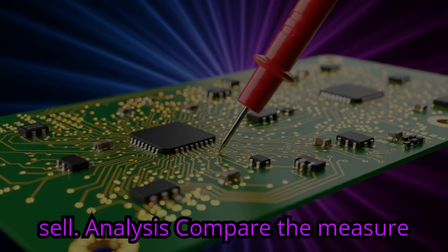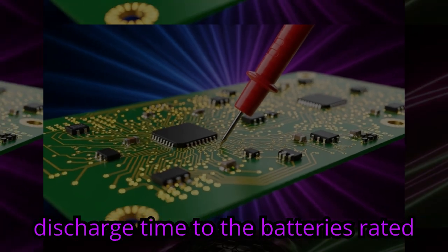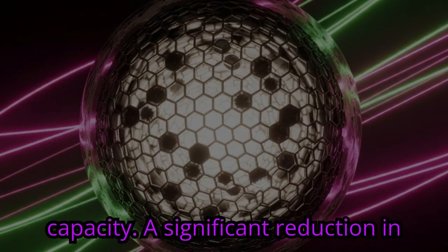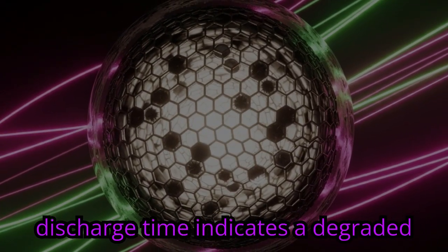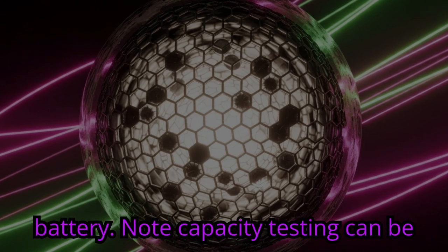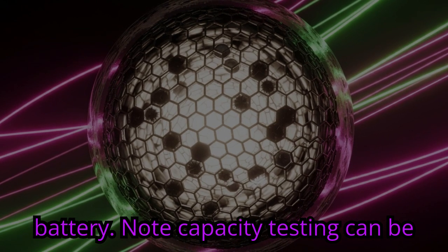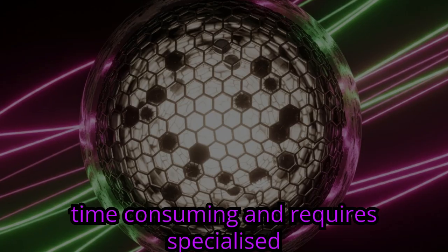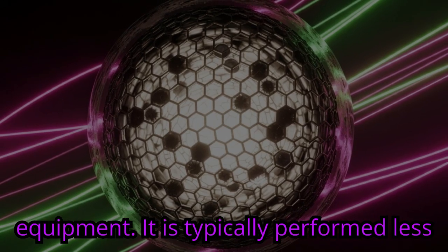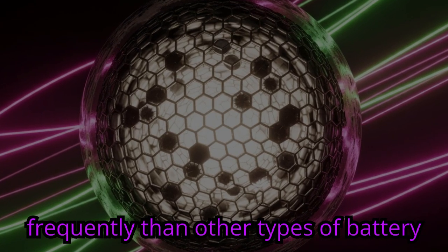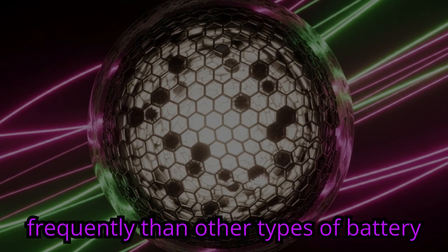Analysis: Compare the measured discharge time to the battery's rated capacity. A significant reduction in discharge time indicates a degraded battery. Note: capacity testing can be time-consuming and requires specialized equipment. It is typically performed less frequently than other types of battery checks.